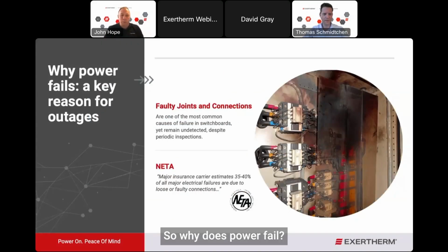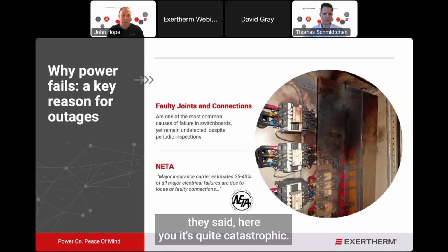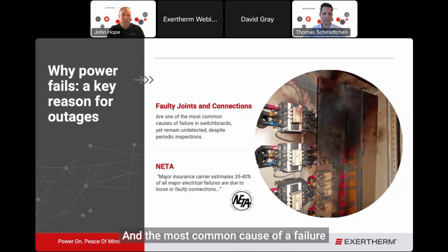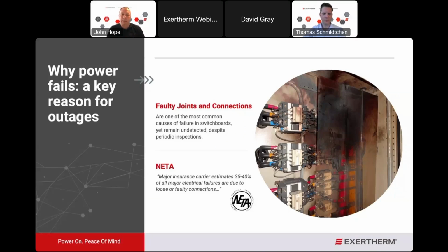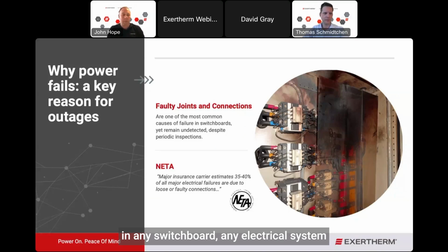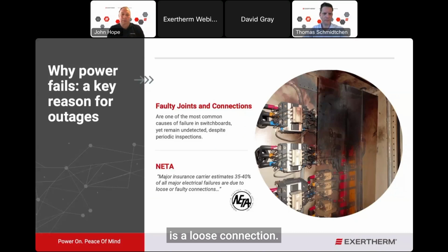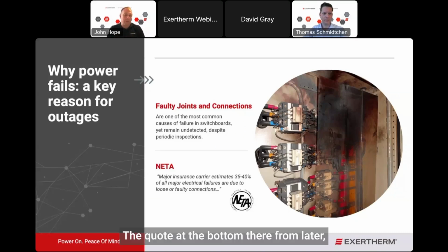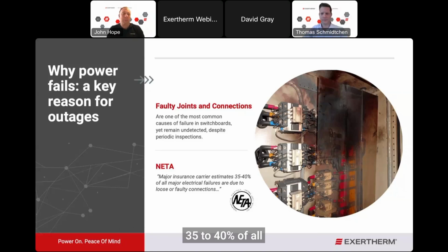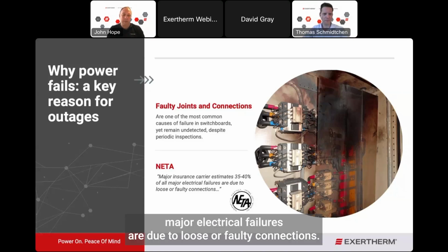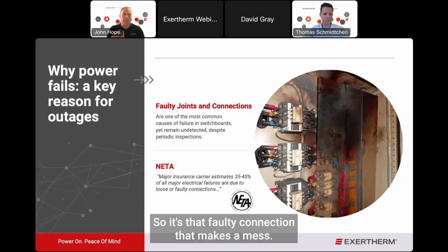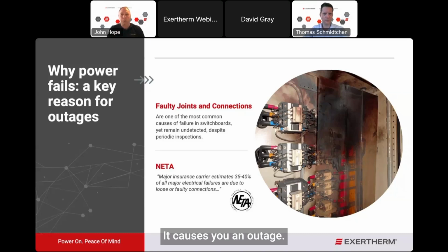So, why does power fail? Well, I think as we can see from this image here, it's quite catastrophic. It's a mess. And the most common cause of a failure in any switchboard, any electrical system, which remains undetected, is a loose connection. The quote at the bottom there from NETA, a major insurance carrier, estimates 35 to 40% of all major electrical failures are due to loose or faulty connections. So it's that faulty connection. It makes a mess. It causes you an outage.